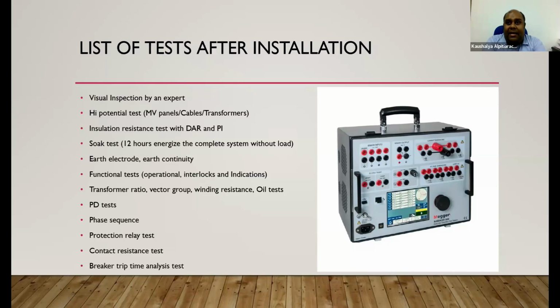No, we don't need, because those ratios are not going to change, even the vector group. Partial discharge test, phase sequence test, protection relay test, contact resistance test, breaker trip time analysis test, as a commissioning test. If you need, you can do it during routine inspections also, but not a must.